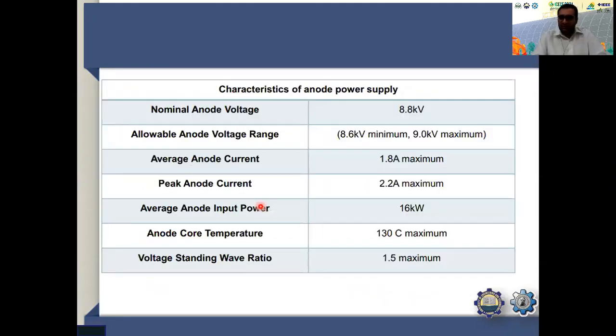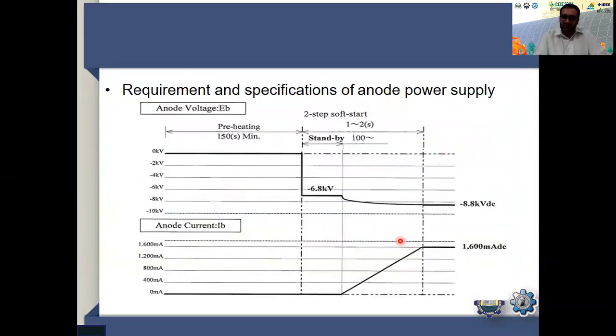The characteristics of this anode power supply are: its nominal voltage is 8.8 kilovolt, with an allowable range of plus minus 200 volt with respect to the nominal voltage. Average anode current is 1.8 ampere. Peak is 2.2 ampere. Its input power should be 16 kilowatt. Standing wave ratio is 1.5, and anode core temperature is maintained at 130 degree centigrade. In addition to all these requirements, the power supply has to follow the waveform characteristics shown in this slide.